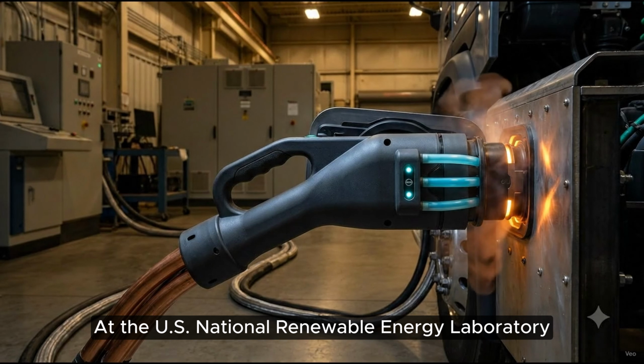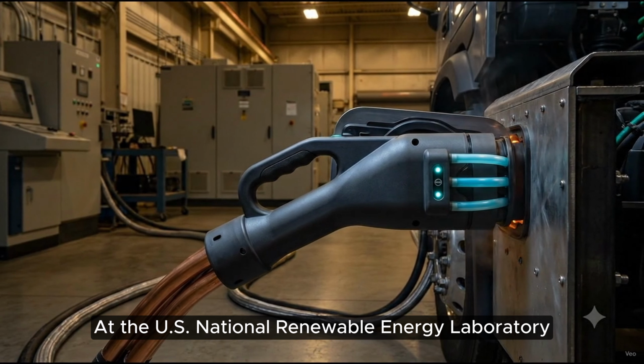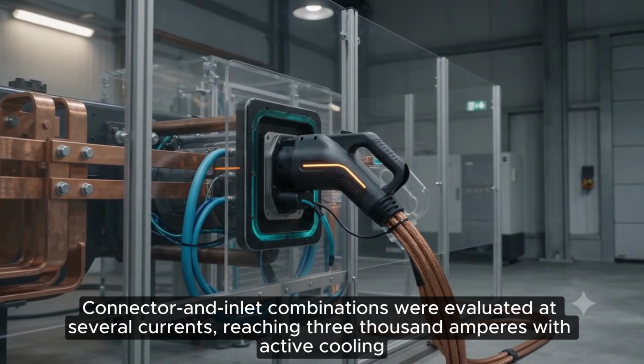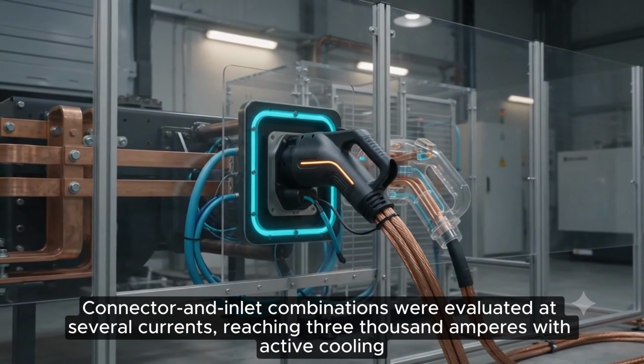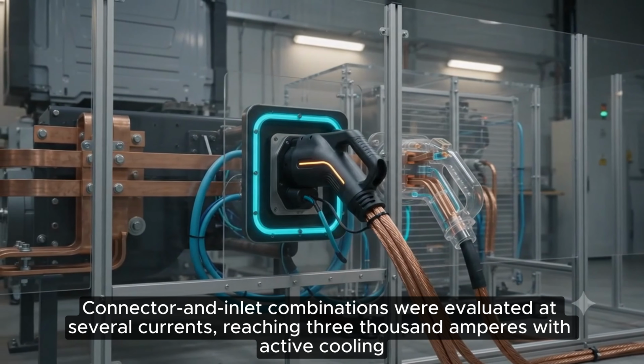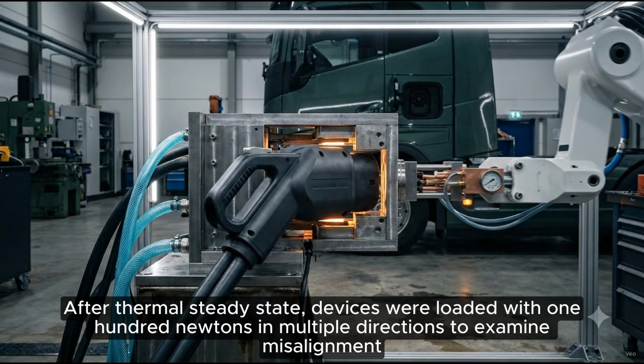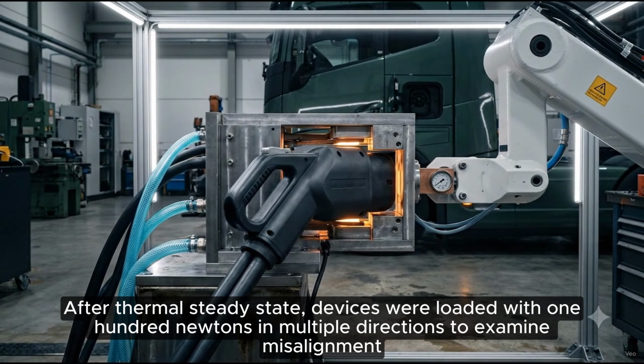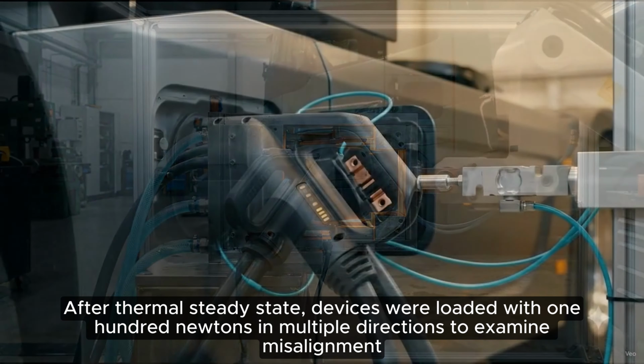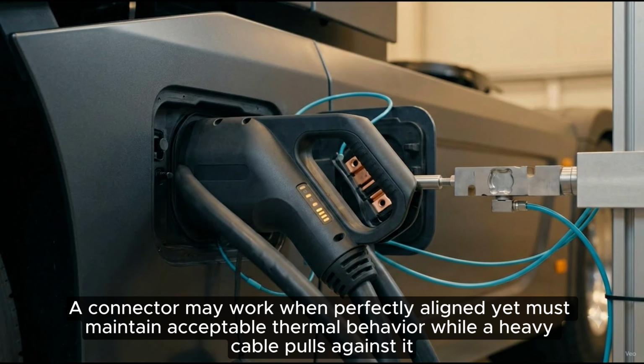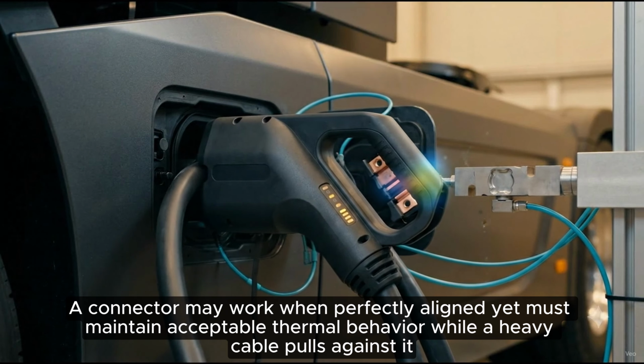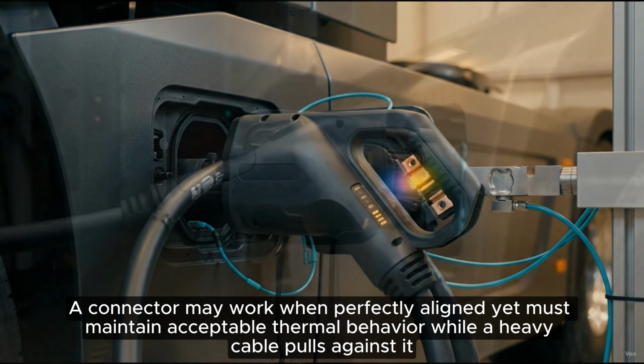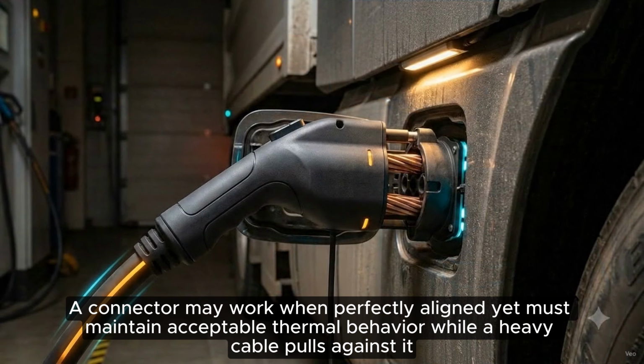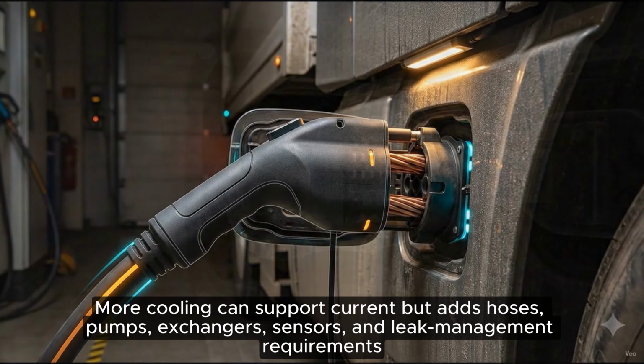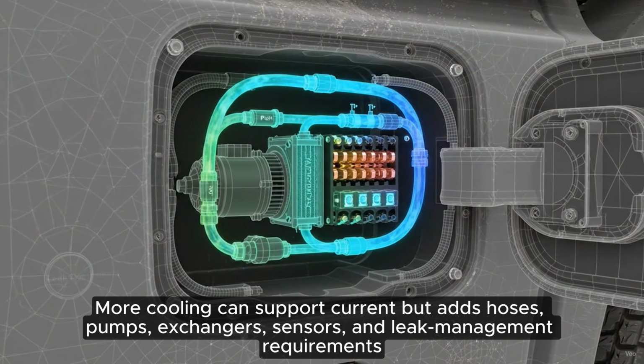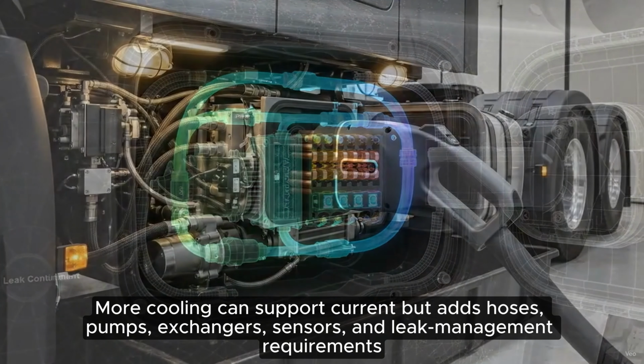At the U.S. National Renewable Energy Laboratory, connector and inlet combinations were evaluated at several currents, reaching 3000 amperes with active cooling. After thermal steady state, devices were loaded with 100 newtons in multiple directions to examine misalignment. A connector may work when perfectly aligned yet must maintain an acceptable thermal behavior, while a heavy cable pulls against it. More cooling can support current but adds hoses, pumps, exchangers, sensors, and leak management requirements.